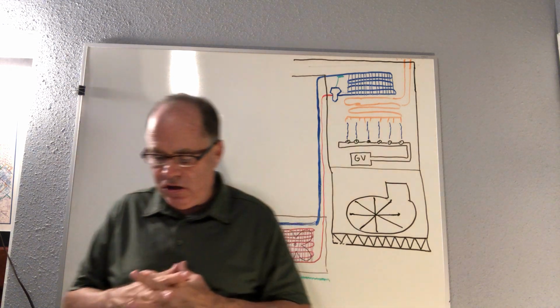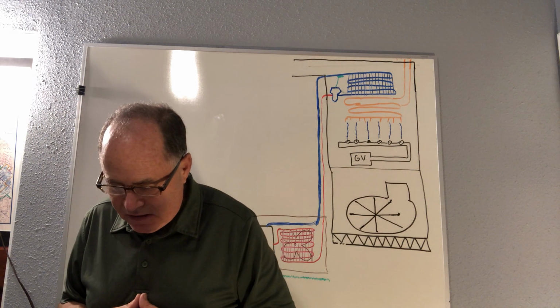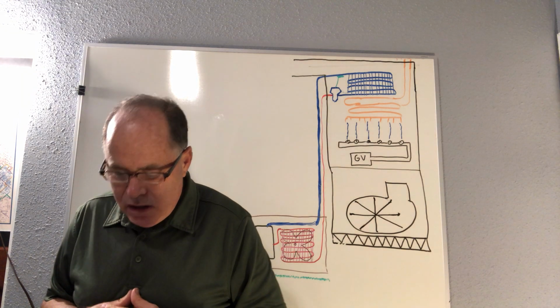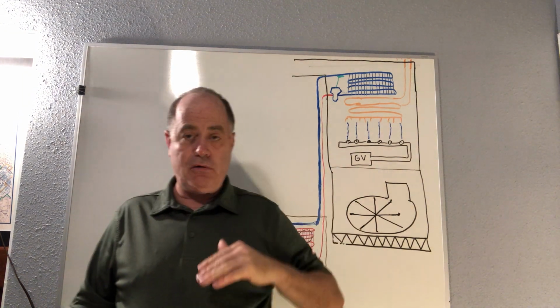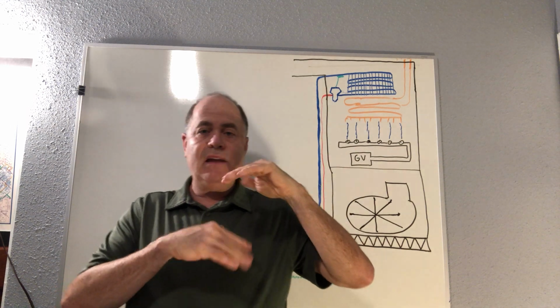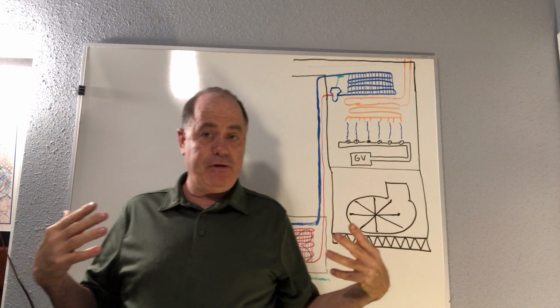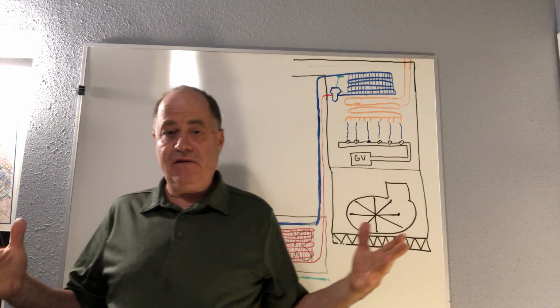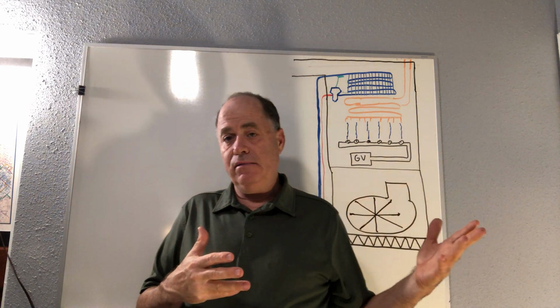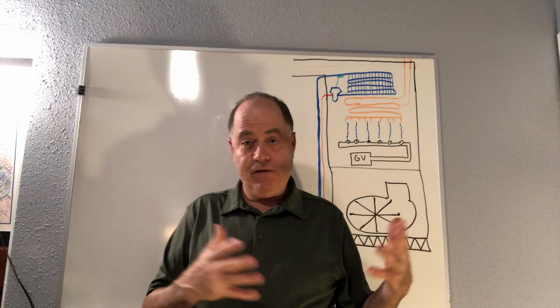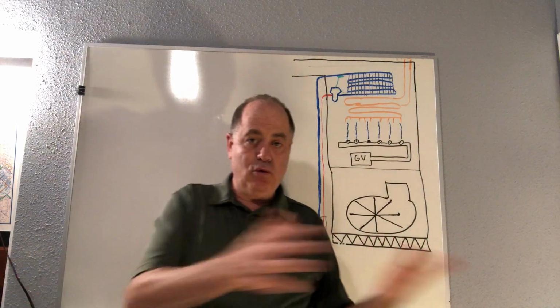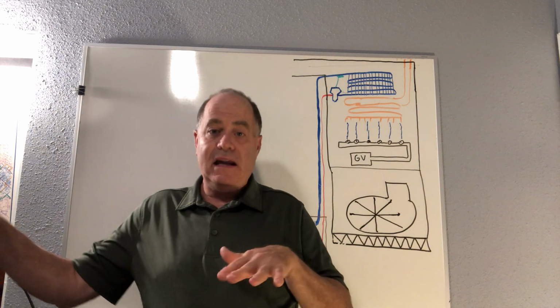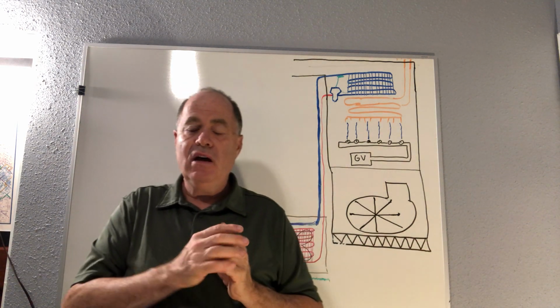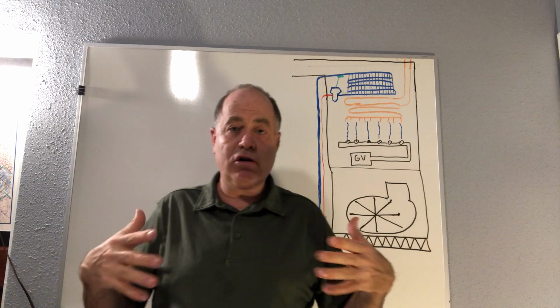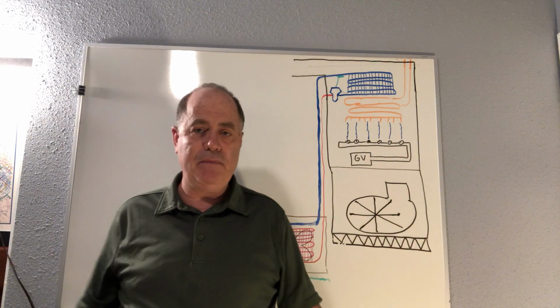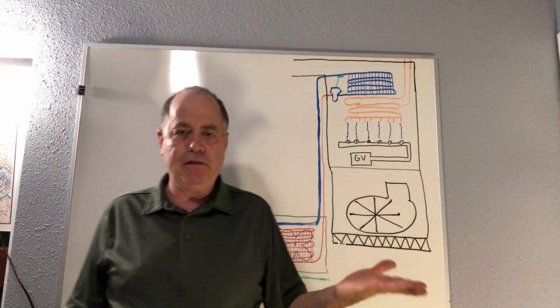And then we have installation in garages for heating systems. Equipment has to be at least 18 inches off the ground, like in a garage, okay? And that's because people store flammable things in a garage, gallons of gas, there's sawdust, there's different paints, and things like that. And if somebody were to knock over a gallon of gas or whatever, and it were to go right into a heating appliance, and that flame was on the burner or a standing pilot or something like that, then you could have a big disaster. So they have to be up off the floor at least 18 inches.